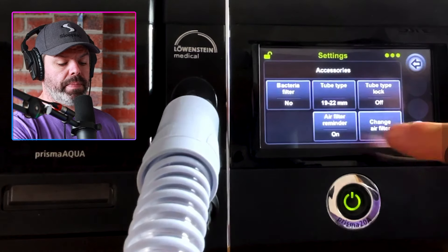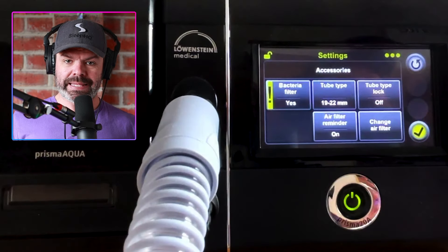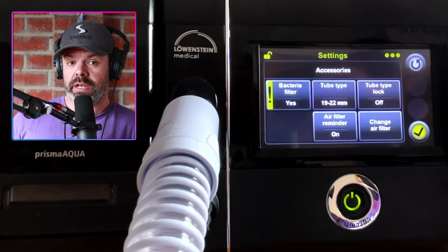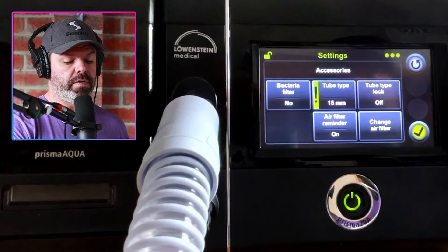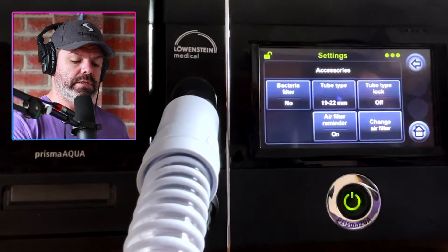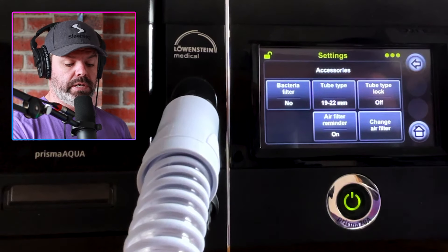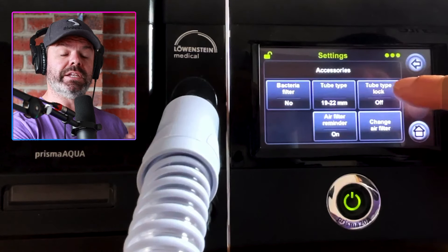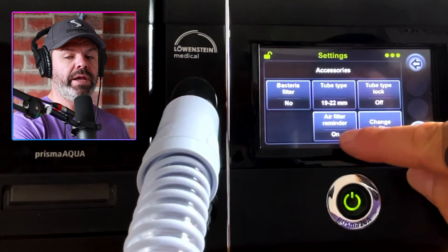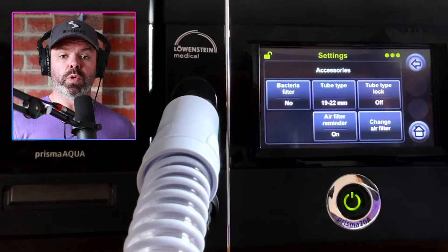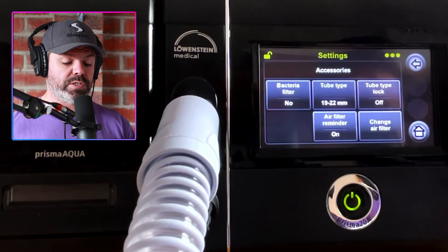Under accessories: bacteria filter — switch this on if you're running an inline bacteria filter in a clinical setting like a hospital; most of you won't need that, so switch it off. We can change the tube type from 15 millimeter to 19 or 22 millimeter depending on your CPAP tubing diameter. Tube type lock is another clinician lock — keep that off. Air filter reminder can be switched on so the device reminds you to change your air filter — probably a good idea.